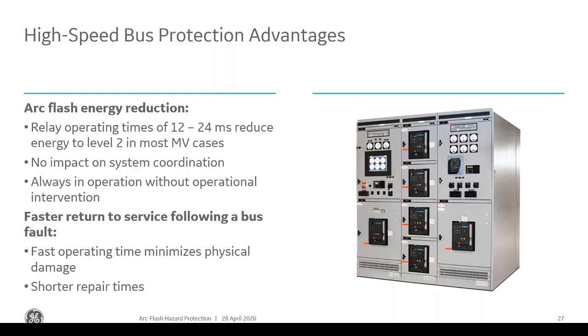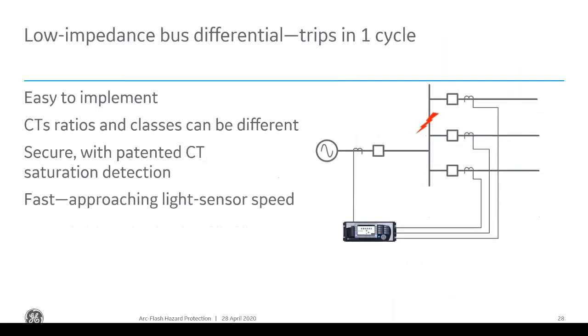It has no impact on system coordination. Bus differential operates with no impact on system coordination; it does not have to coordinate with anything. It's just going to operate for faults on the bus. It also operates without operational intervention, unlike the maintenance switch. Remember, the maintenance switch needs to be put into maintenance mode when you're working there. The bus differential is always there, and it's always going to operate. And because of the fast operation, it minimizes damage to the equipment. That means shorter repair time, so less downtime for your process. So there are a lot of advantages to using low impedance bus differential.